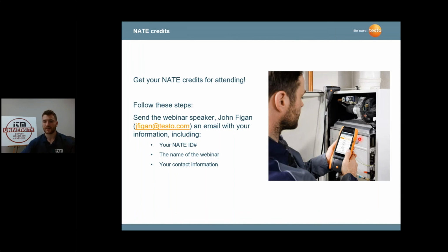So John, we have a few questions that have come in. Joel is asking, what is the biggest factor for soot formation in a natural gas-fired commercial boiler? Soot is the result in a natural gas-fired burner, did he say? Yes, exactly. Typically you're going to see the soot in oil burners, and that's the result of smoke. Smoke soots up the heat exchangers and the internal of the stack. As far as natural gas fuel, I have had very little information on soot buildup. It's primarily with oil, and that's a result of the smoke that's caused by the burner itself. Perfect, I think you got it there.